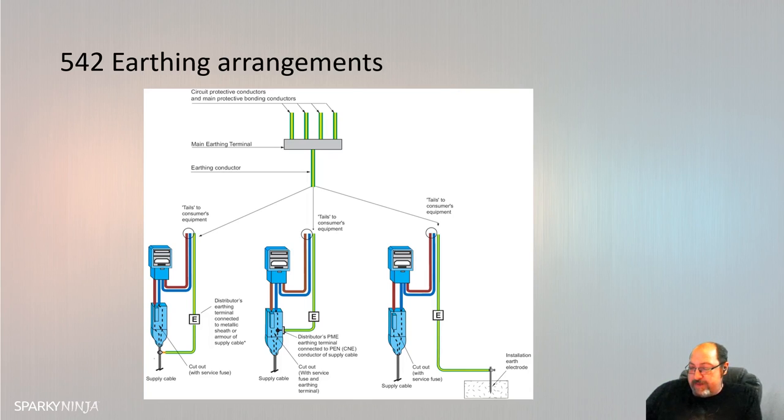There'll be a little mention on that in a minute on the next page on table 54.1, but we'll also look at sizing of protective conductors and bonding conductors. We'll be saying if the cables run unsheathed without mechanical protection, so just like a single green and yellow cable that's just clipped along, then we'll have to size it to a level for consideration of mechanical strength.